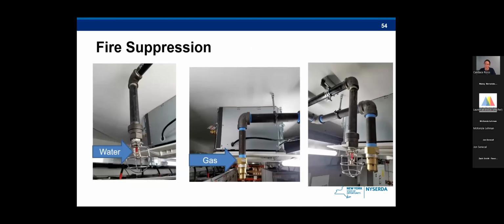So a little bit more visual to the fire suppression systems. This is from a project that's located downstate. So this container specifically had two separate types of suppression. It has the water fire suppression. So you can see basically that they have a fusible link that will allow water to flow, and basically the lead fusible link is melted out from the heat.